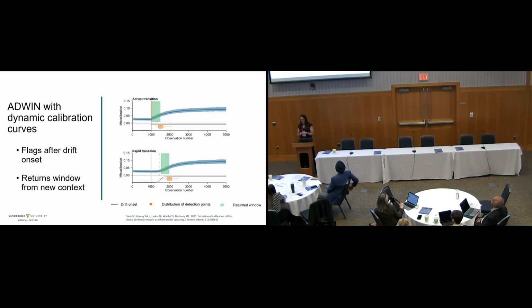So in simulation studies where we went from calibrated to a whole variety of different types of miscalibration, and we did it quickly or abruptly or very gradually or seasonally, what we found was, this is a pretty dense plot, but if you look at the orange whisker plot along the bottom, that's the distribution of detection points. And so we had very few false positives. The system tended to flag that drift was happening after the simulated drift actually did happen. So that's reassuring. And the green box represents the median window that was returned, and those are also after that red line of where drift started. So it was, in fact, giving us data that reflected that new calibration context.